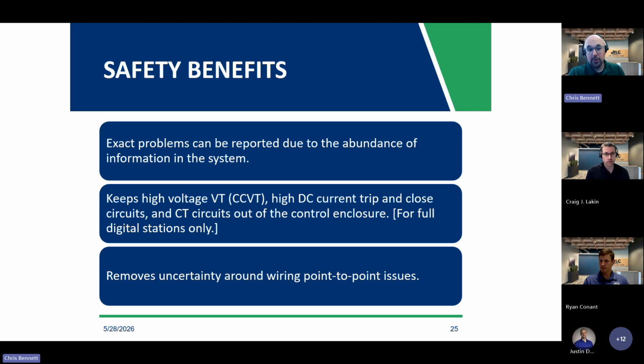On a physical level, we're also keeping high voltage from VTs and CCVT circuits, as well as the high DC current trip circuits, close circuits, and CT circuits out of the control enclosure. Now, keep in mind that's for full digital substations only. If you opt for a hardwired design, unfortunately, we still will have those inside of the control enclosure, but it is in one central area now and not spread through multiple panels where it might be difficult to locate which wire goes where.